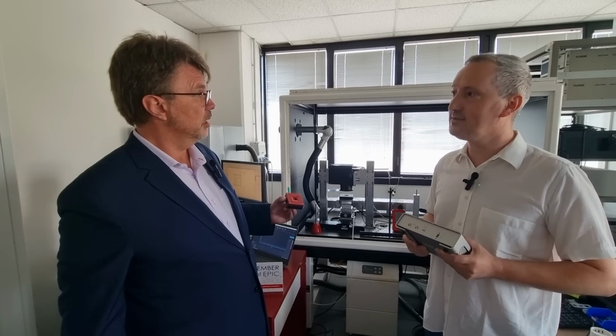Correct, we have our sensors sent to them, they double check and they specify that they measure within a certain very tight accuracy. Wow, so that means when I purchase a LaserPoint sensor, basically I've got that reference standard in my hands right now. Correct. Actually, it is not the real reference, but it is something measured against that reference.